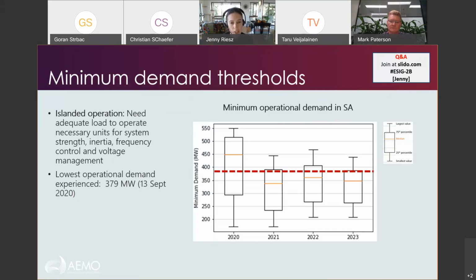The chart on the right is showing you the amount of load that we need in South Australia to operate a secure system that has all of those services just in the South Australian grid if it's operating as an island. And there's a bit of a range in the box and whisker you can see there because of the different unit combinations that might be online. So if we're using the very, very bottom combination, we may get away with around 200 megawatts or so to run that unit combination.